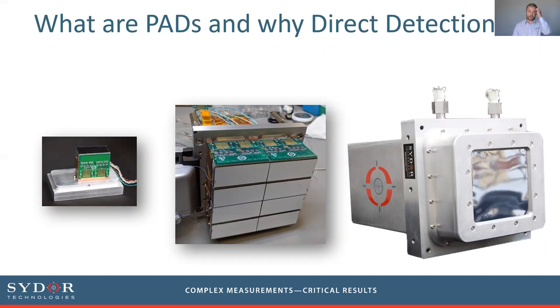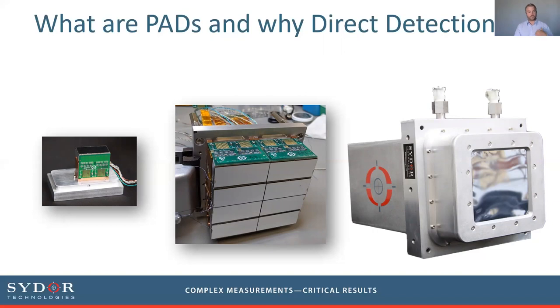It's also a direct detector, as opposed to an indirect detector which has typically been used for x-rays in the past. An indirect detector setup uses something like a scintillator which converts incoming x-ray photons into visible light, and then a visible light camera reads the visible light photons coming off the scintillator. There are several conversion steps happening in indirect detection, which degrades quantum efficiency, degrades the point spread function, and means the temporal response may not be capable of reaching these megahertz imaging regimes.